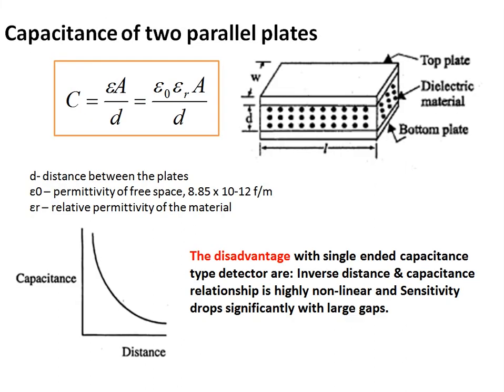The equation for the capacitance type differential pressure transmitter can be derived as follows. The capacitance of two parallel plates is given by epsilon × A / D, where epsilon-naught is the permittivity of free space and epsilon-r is the relative permittivity or dielectric constant of the material. A disadvantage of this two-plate arrangement is that the relationship between capacitance and plate distance is inverse, and sensitivity drops significantly with large gaps.